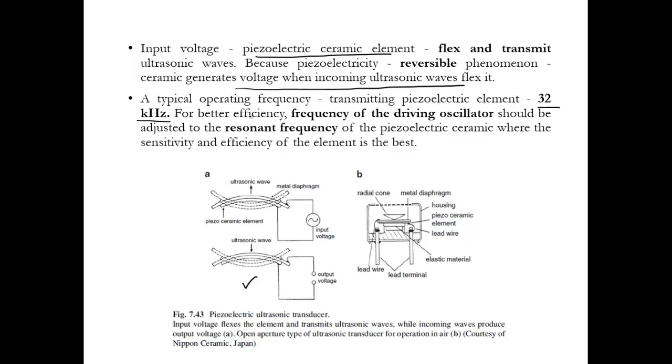And as we have already discussed, for better efficiency, the frequency of the driving oscillator, or you can say the voltage input, should be adjusted to the resonant frequency of the piezoelectric ceramic material, because the sensitivity and efficiency of the element is best in that case.